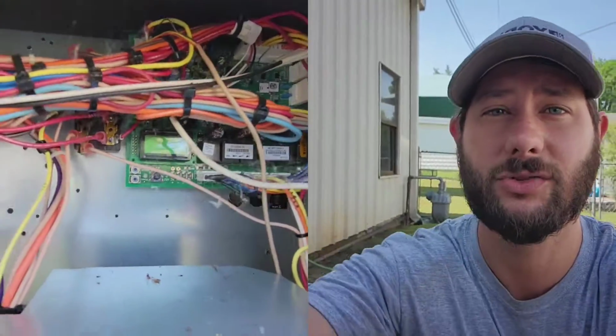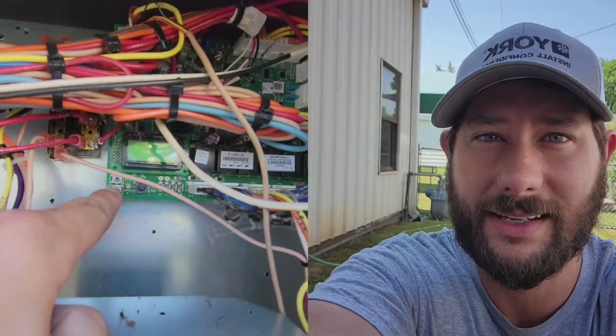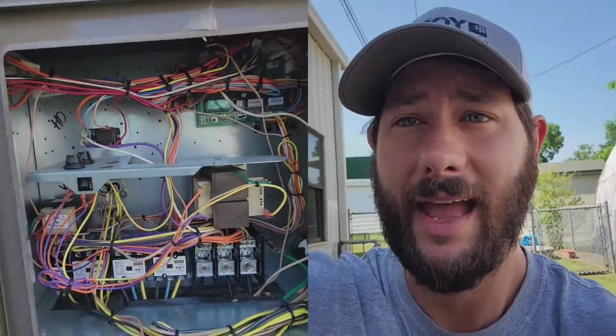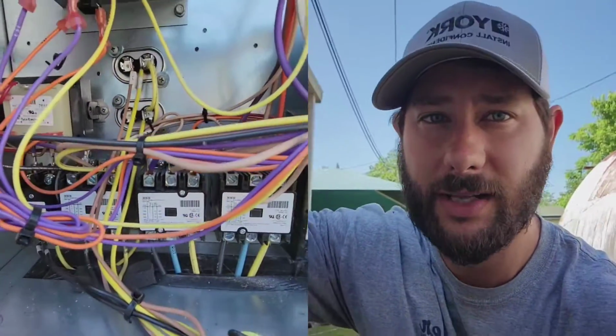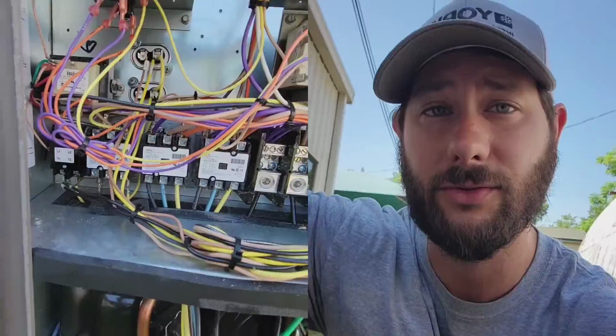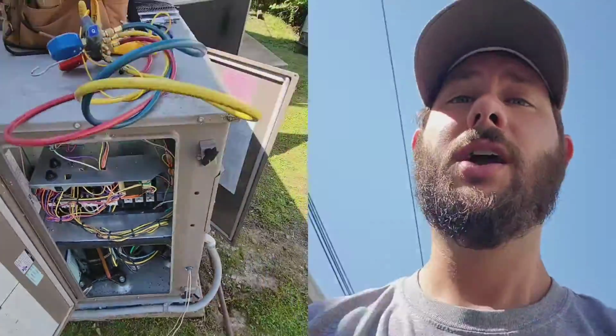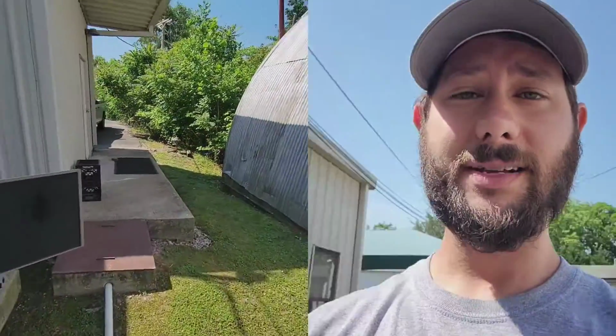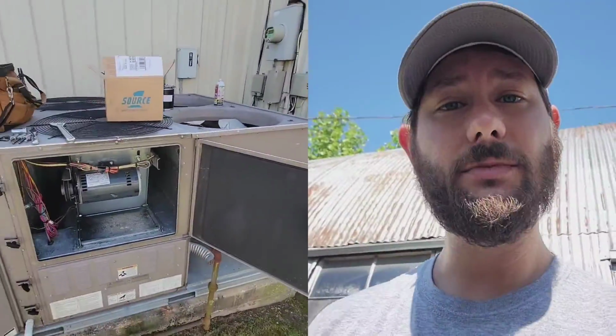You've got your simplicity control, your little joystick, your enter and cancel button. Then you've got your relays, your capacitors for your outdoor fan motors. There are two outdoor fan motors on this system. One of them has bad bearings, and I'm going to show you how to check the bad bearings today.